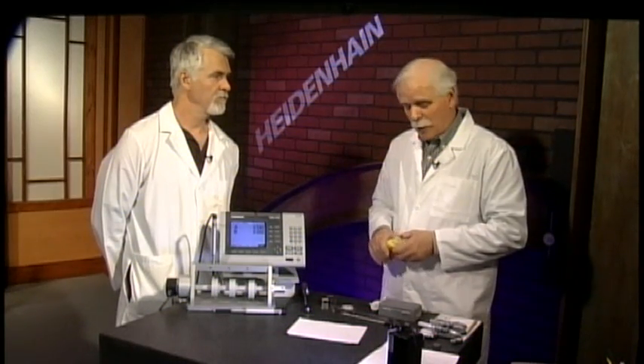On the rare occasions there is oil needed, which is very rare from your point of view. On the internal, that's a different story. But on the external, again, a good high-quality oil from one of the manufacturers that you know and trust, very sparingly. Always on either a rag, a chem wipe, or a needle if you're just going to put a dab. Less is better. The tools really are made to be run pretty well dry from the outside. And they're precision tools, so that's why you can run them dry, is you have very, very polished surfaces in most cases. Right? Yeah.